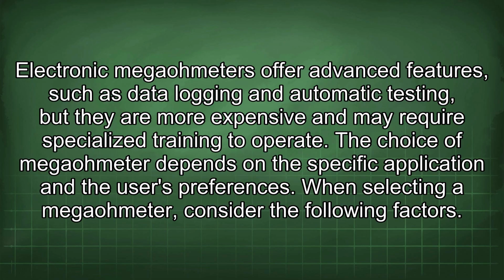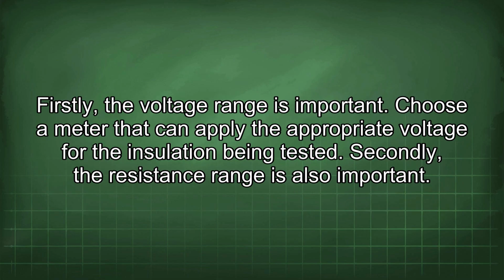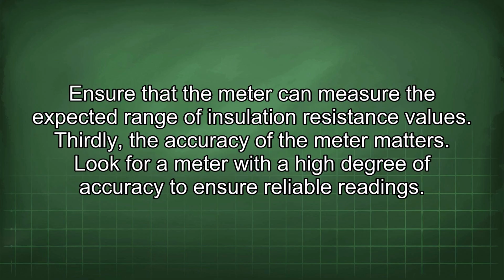When selecting a Megaohmeter, consider the following factors. Firstly, the voltage range is important. Choose a meter that can apply the appropriate voltage for the insulation being tested. Secondly, the resistance range is also important. Ensure that the meter can measure the expected range of insulation resistance values.